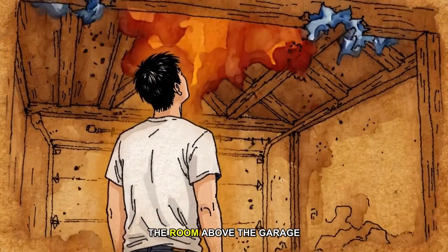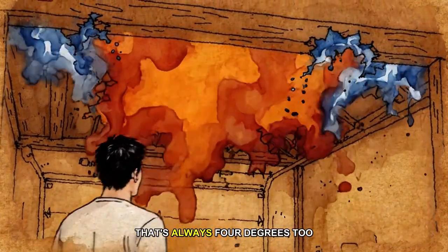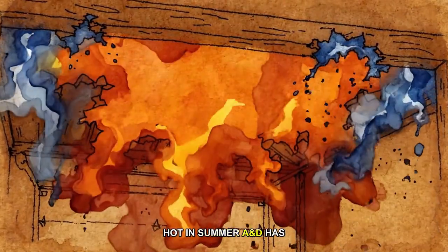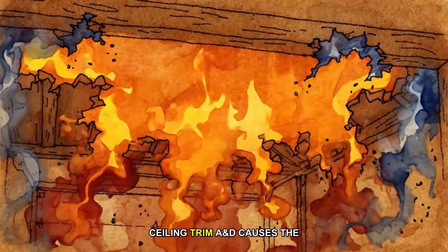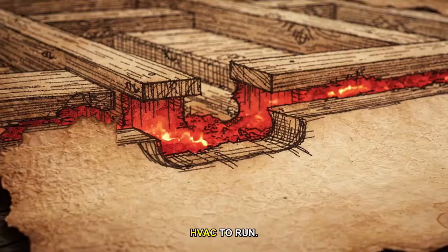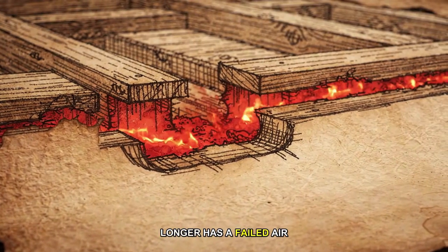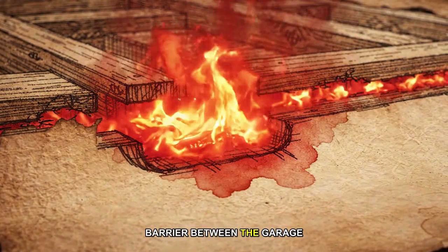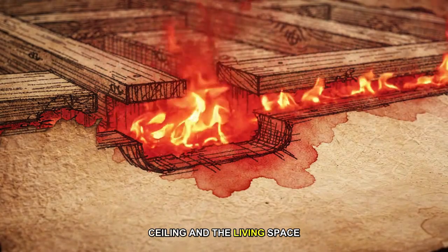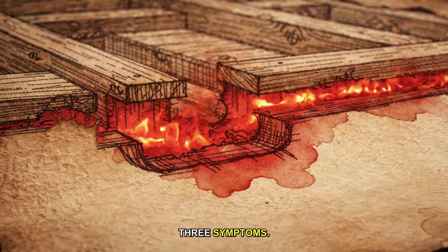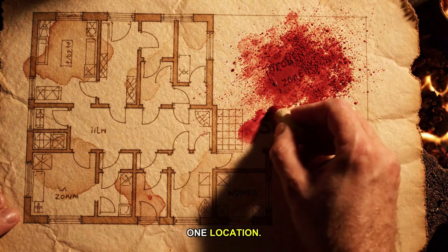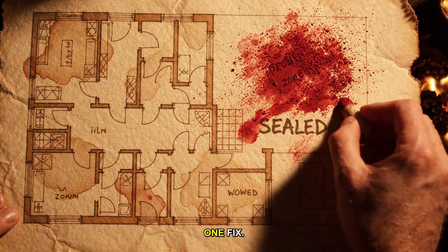The room above the garage that's always 4 degrees too hot in summer and has dusty ceiling trim, causes the HVAC to run longer, has a failed air barrier between the garage ceiling and the living space above. 3 symptoms. 1 location. 1 fix.